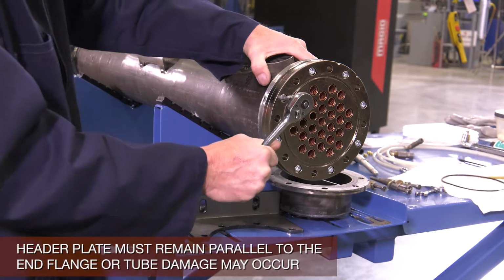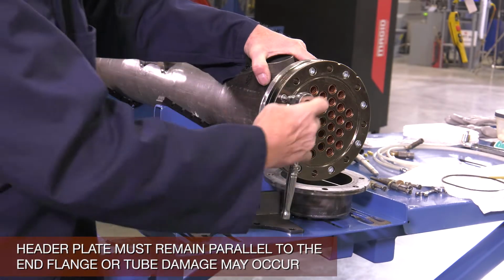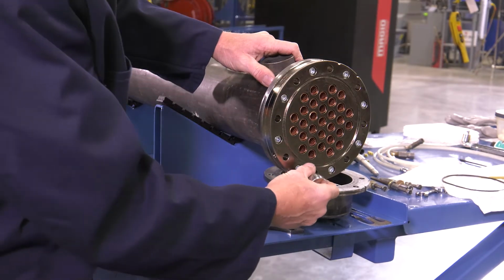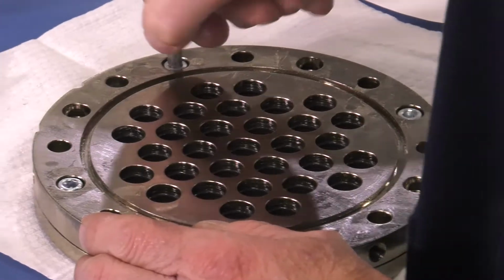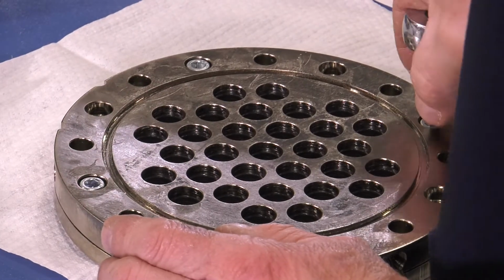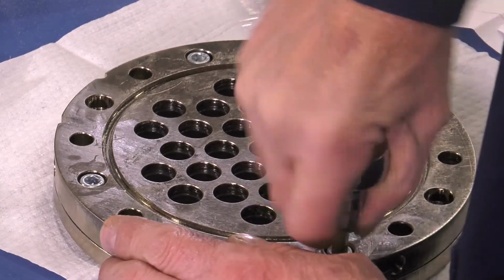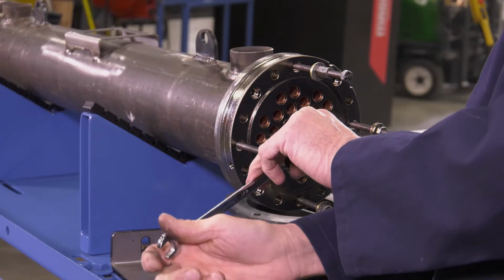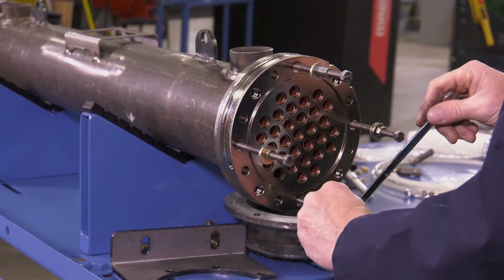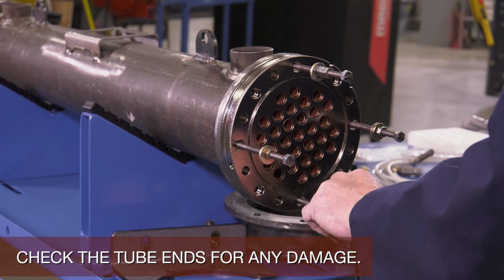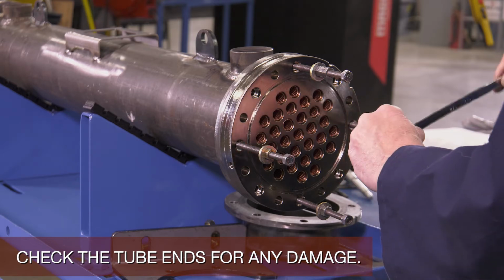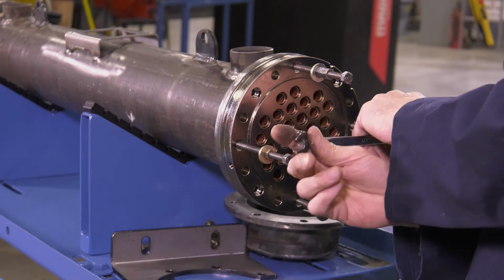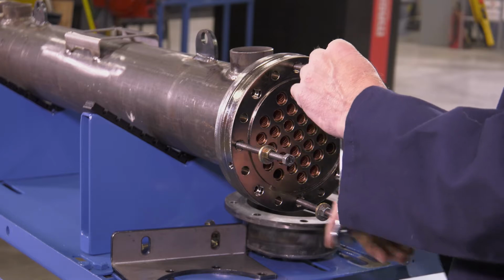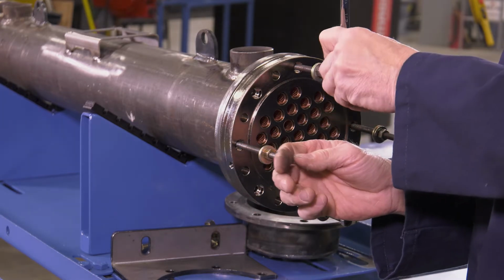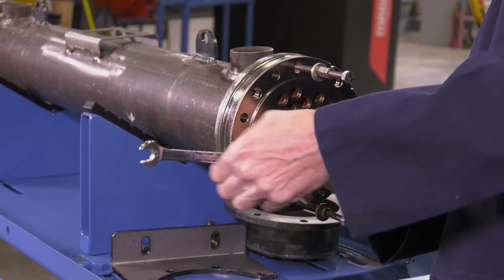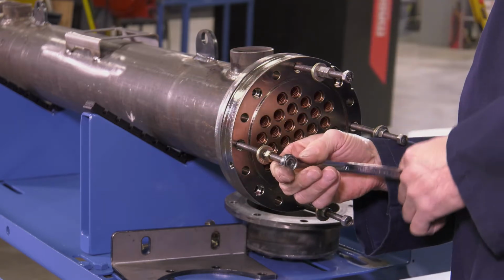Remove the 1 1/4 inch header plate retainer bolts holding the header to shell flange. Remove the 5/8 inch cap bolts holding the two header pieces together. Insert the back-out bolts with at least 3 inches of thread into the back-out holes until tight against the shell flange. Once the back-out bolts are in contact with the end flange, turn the back-out bolts no more than 1/2 turn per bolt to remove the header plate.